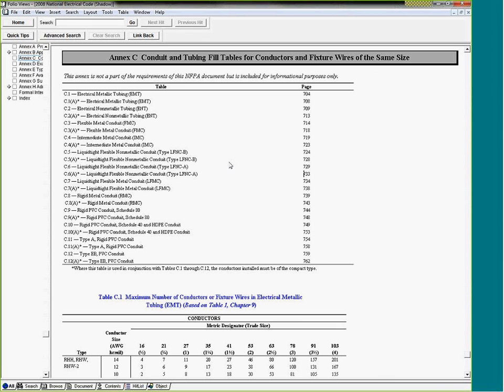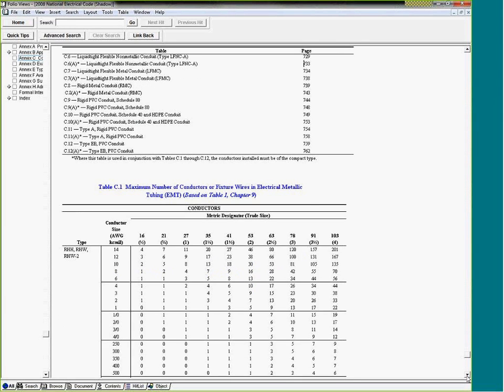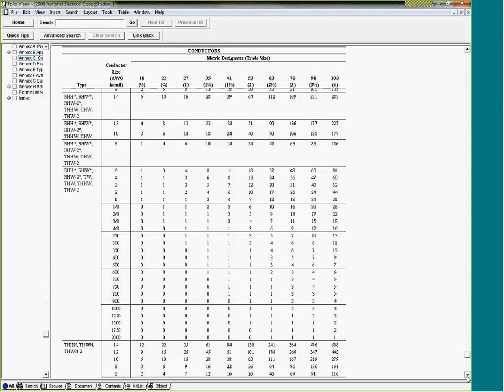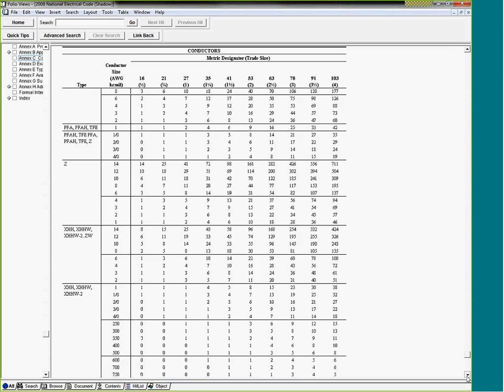You go directly into the conduit fill tables, and for EMT, guys, I want to make sure you notice that when this is EMT, we have the asterisk here, or the little star. This is for compact conductors, these special type of conductors, compact. You can see all the conduits that God created are listed in here. That's your starting point. Every conduit has two tables, one for compact conductors and one for non-compact conductors. All right, so let's just take an example here. Since we were using flexible metallic, let's go all the way to flex and see what we can do for flex. Keep going all the way.